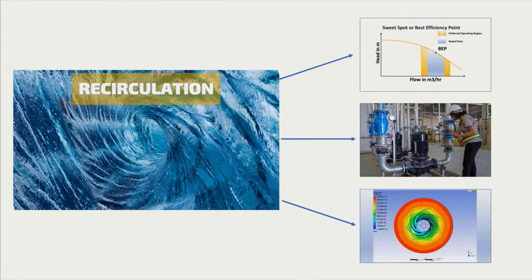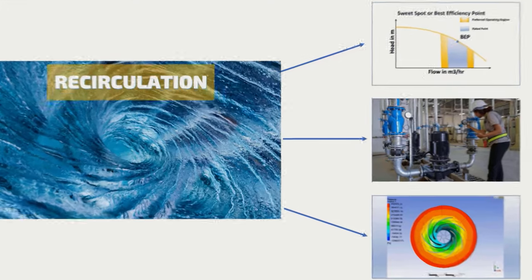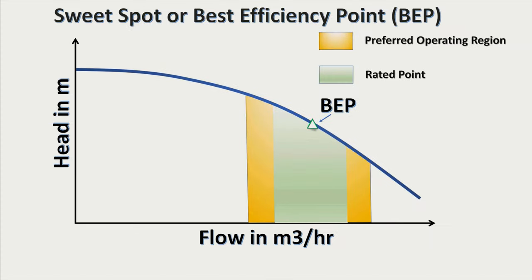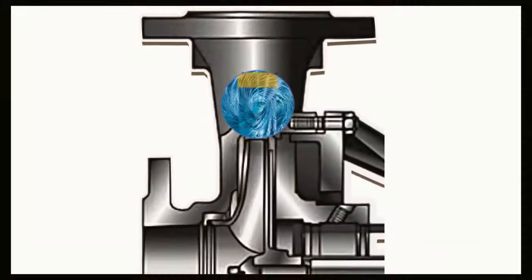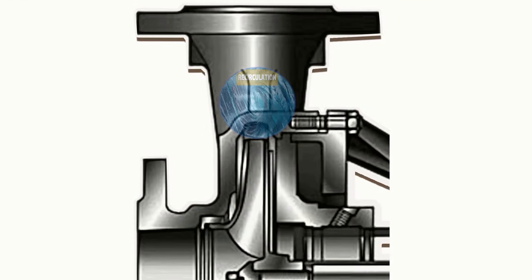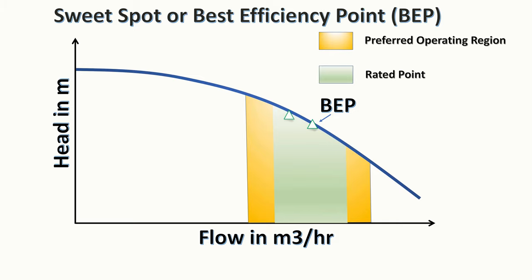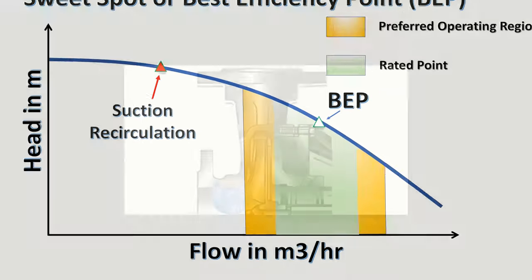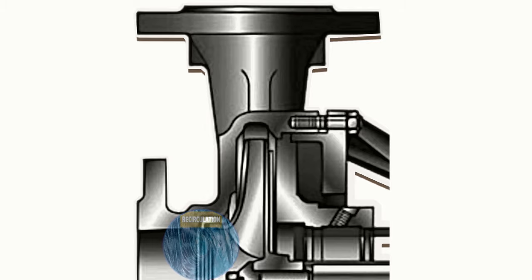Recirculation can happen in a pump system due to three possible reasons. The first is when the pump operates away from its sweet spot, called the Best Efficiency Point (BEP). This is the flow point where the pump yields maximum performance and minimal recirculation. Deviating away first results in discharge recirculation, and deviating further results in suction recirculation, which impacts the Net Positive Suction Head required and amplifies cavitation.